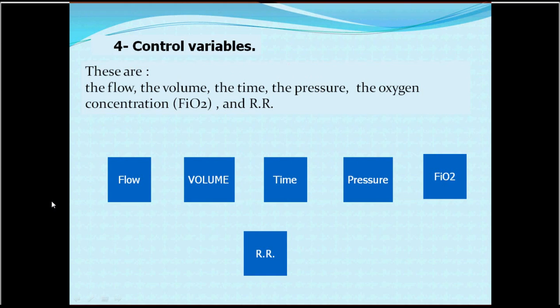The fourth component is control variables. When we deliver air or breath, we consider its physical characteristics: it has a volume, a flow, it is delivered in a certain time, developed at a certain pressure, with a certain FiO2 composition, and these data are repeated at a frequency — the respiratory rate per minute. These are the control variables — the physical characters of the breath itself.